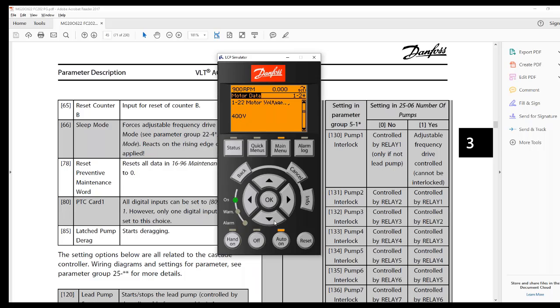rating, the motor voltage, motor rated frequency, current, and RPM. There's other parts of the motor data, I'd say, of the motor model, which you have the stator resistance, rotor resistance, and reactance, and such. The automatic motor adaptation will adjust these. It does a tuning on the motor and puts these numbers in basically based on sensing from the output current sensors and such. So this will also take the motor cables into effect, all the resistance and capacitance.